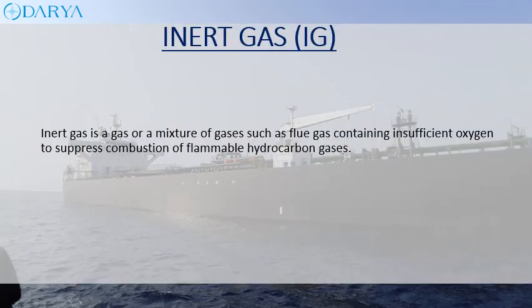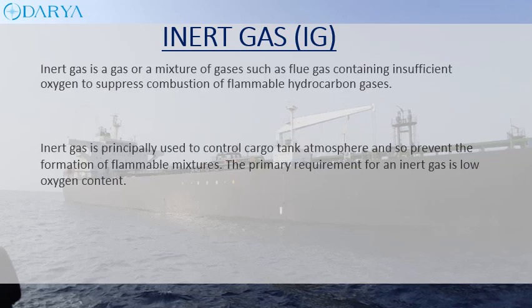Inert gas is a gas or a mixture of gases, such as flue gas, containing insufficient oxygen to suppress combustion of flammable hydrocarbon gases. Inert gas is principally used to control cargo tank atmospheres and prevent the formation of flammable mixtures. The primary requirement for an inert gas is low oxygen content.